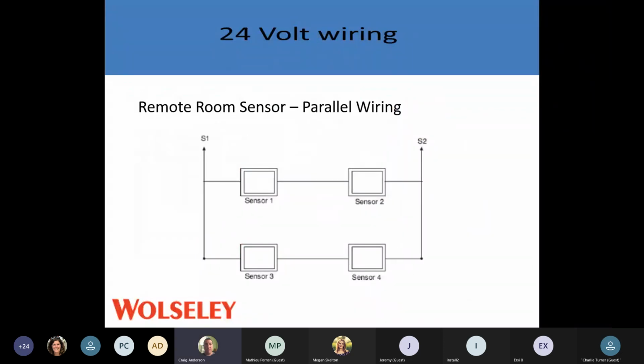Room sensors are a great thing too if you're running into issues like that hallway's always hot, or we're into a commercial unit. When we get to an ion stat or an observer stat, we can add multiple sensors to it, so it will take the average of that room. So if it's in a small commercial place and someone's always hot, someone's always cold, you can put multiple sensors in that area, or you could even do it in a house if you'd like. If there are double floors and stuff like that, it'll take an average of those 4 sensors to heat and cool the space.